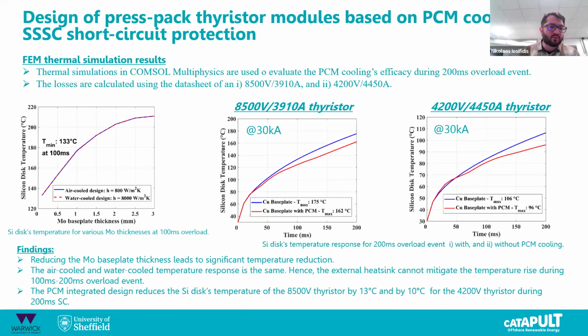So as we can see on the left graph, technically what I told you earlier, because the overload event is very quick, around 100 milliseconds, any type of external cooling solution you have is not fast enough, so it cannot mitigate the heat quickly. So what you can do is integrate something in the existing structure. Now thyristors have anode and cathode, which are copper blocks. So by integrating this bismuth alloy phase change material, you can have simultaneous conduction of current, because this is a liquid metal, and also you can have phase change cooling.